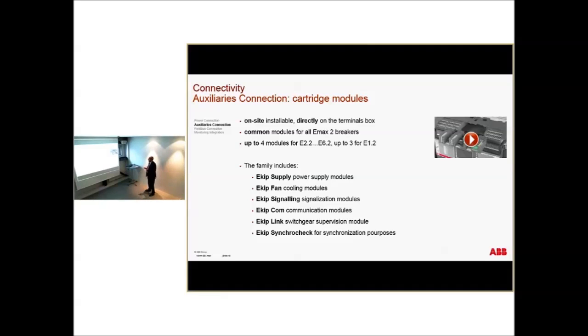Signaling, definitely, I'll show you later on, there is a big improvement in the signaling. There is no more protocol converter. In cases like DeviceNet, a protocol converter creates a sort of bottleneck. In this case, you have independent, specially designed cartridge modules for signaling. This is the only breaker in the market to have an internal monitoring system. Better to show later on. Again, we have the SynchroCheck that I explained before, a very small module that is also fitted here and avoids having an external device.